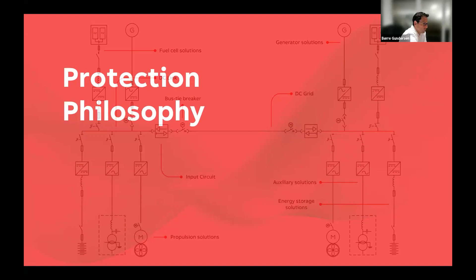So the whole protection philosophy is different and needs to be taken seriously. It's not typically - if you are into this you would know time selectivity is what is used on AC typically. This wouldn't work here because the short circuit is in the range of few milliseconds, very few milliseconds, sub-millisecond, instead of typically 15 to 30 milliseconds. So breakers, standard breakers will not work.